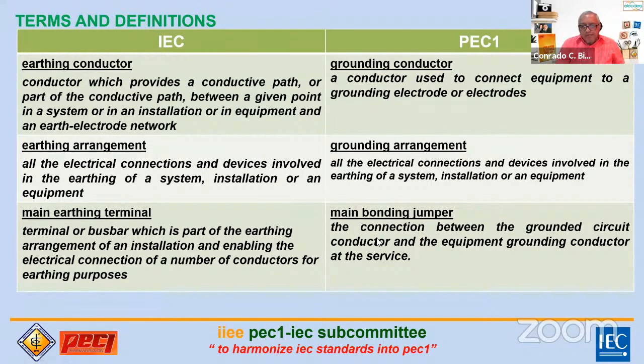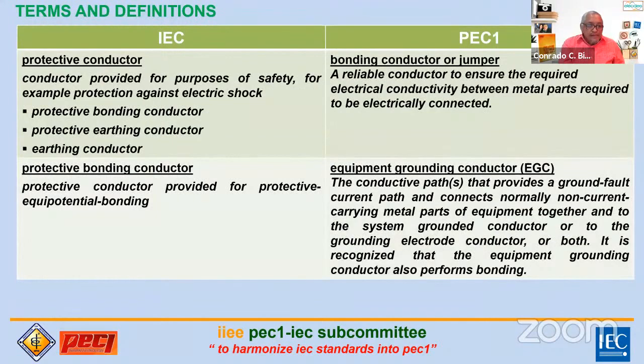So the main bonding jumper is the connection between the grounded circuit conductor and the equipment grounding conductors at the service. It seems this comes out at the service. But in IEC, it's just before the installation, where you have the main earthing terminal block. Anyway, we have a diagram based on IEC later. This is important, that we know the equivalent bonding conductor or jumper, and what the protective conductor is.